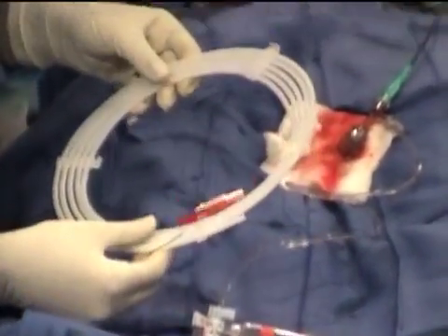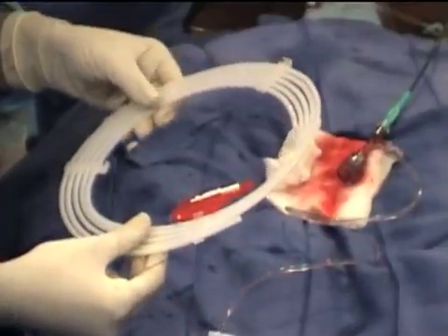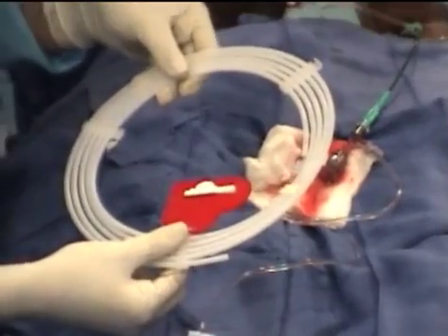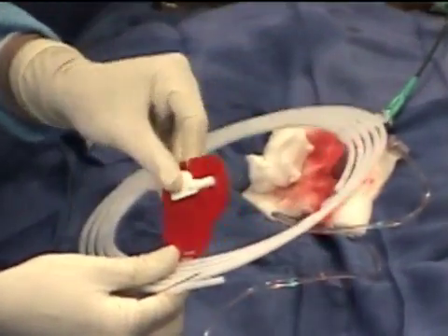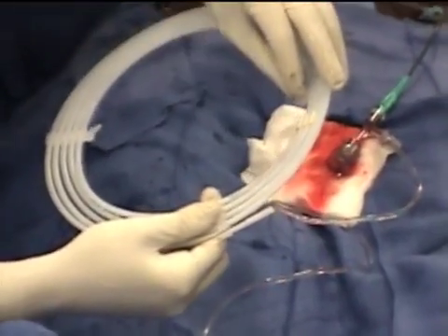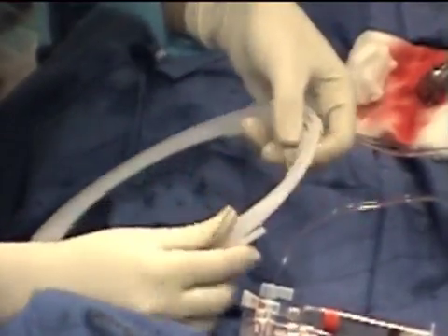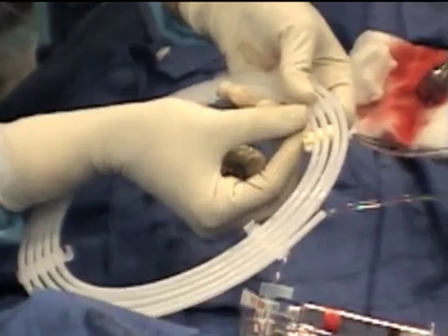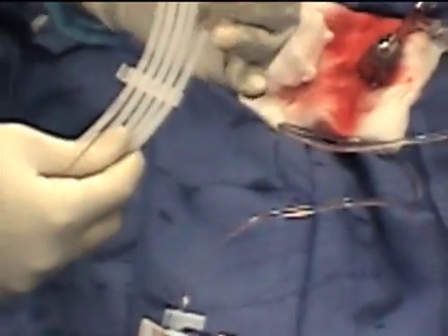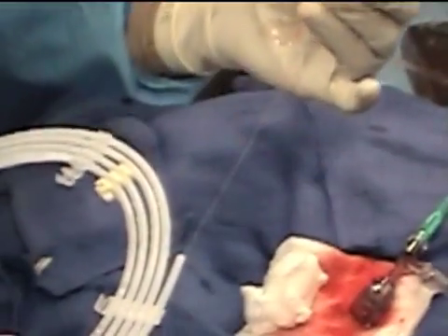Good. So, if you see here the Rotawire, which is a 300 centimeter stainless steel wire, comes this way once you take it out from the packet. Very important, this is the Rota clip, which you can take and keep aside. And if you see here, this is the distal end and this is the proximal end, which comes with the blue covering. Now, you cannot take it out unless you have disconnected the distal end.